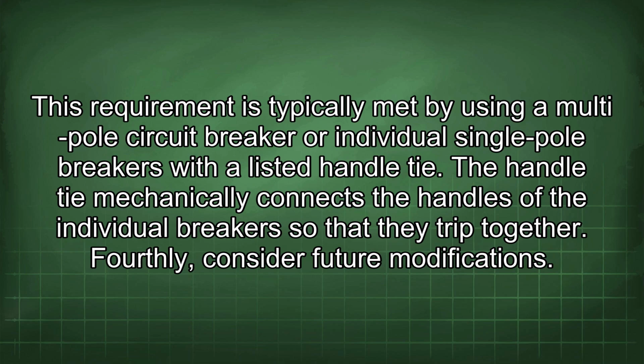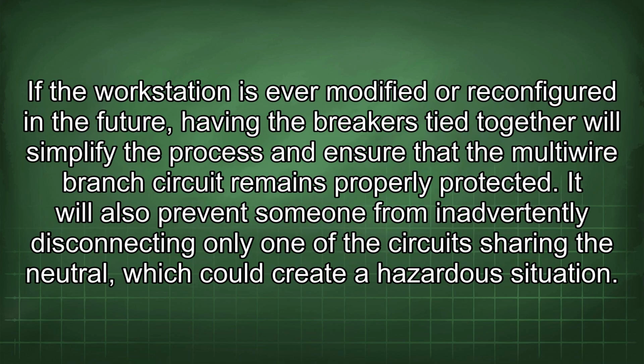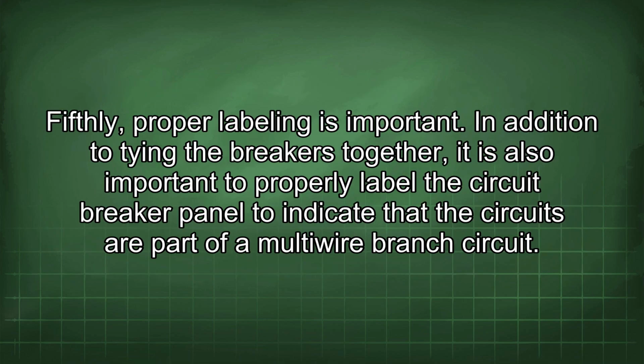Fourthly, consider future modifications. If the workstation is ever modified or reconfigured in the future, having the breakers tied together will simplify the process and ensure that the multi-wire branch circuit remains properly protected. It will also prevent someone from inadvertently disconnecting only one of the circuits sharing the neutral, which could create a hazardous situation. Fifthly, proper labeling is important.